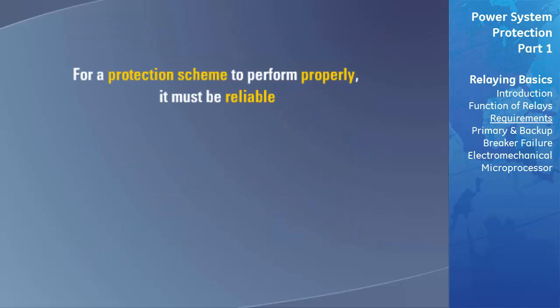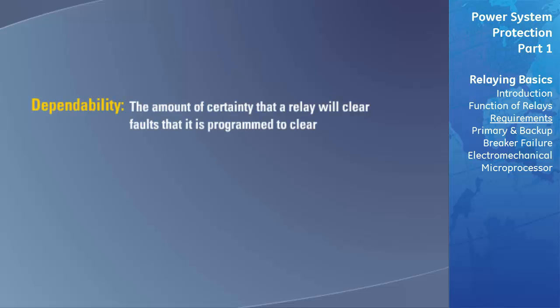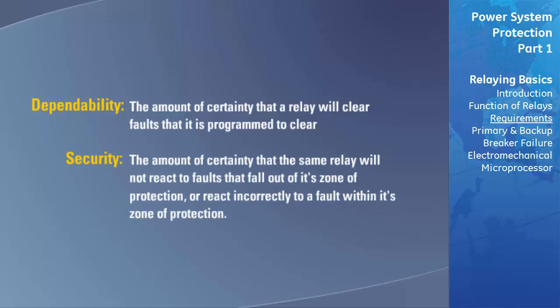For a protection scheme to perform properly, it must be reliable. With respect to protective relaying, reliability is made up of two components, dependability and security. It is important to understand the difference between dependability and security. Dependability is the amount of certainty that a relay will clear the faults that it is programmed to clear, whereas security is the amount of certainty that the same relay will not react to faults that fall outside of its zone of protection or react incorrectly for a fault within its zone of protection.